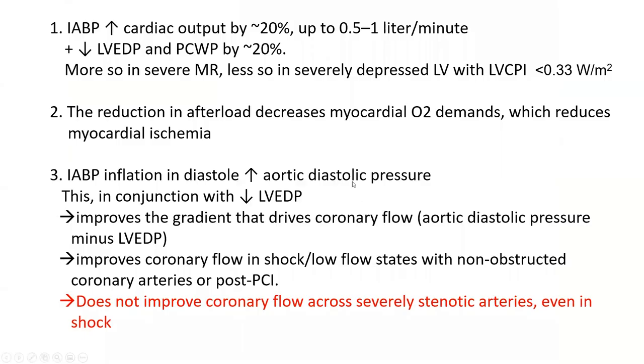So here is a summary of the physiological effects of balloon pump. Balloon pump increases cardiac output by approximately on average 20% and by up to 0.5 to 1 liter per minute. You need to know those numbers. And it reduces LVEDP and wedge pressure by 20%. This is again related to the reduction in the pressure afterload and the facilitation of the increase in stroke volume. Now, those numbers vary according to several features. For example, in severe MR, you're going to increase the cardiac output potentially more than that.